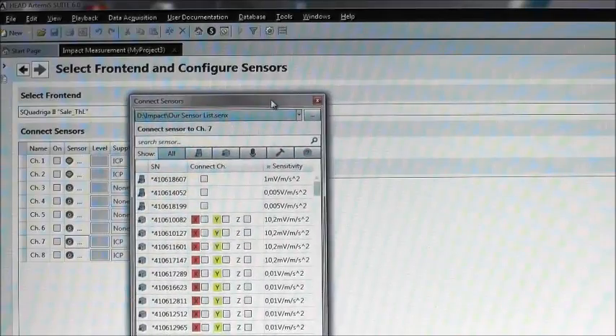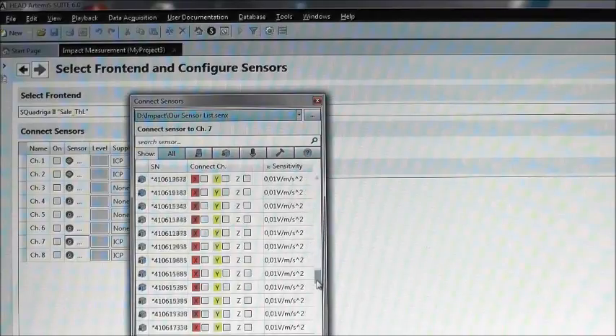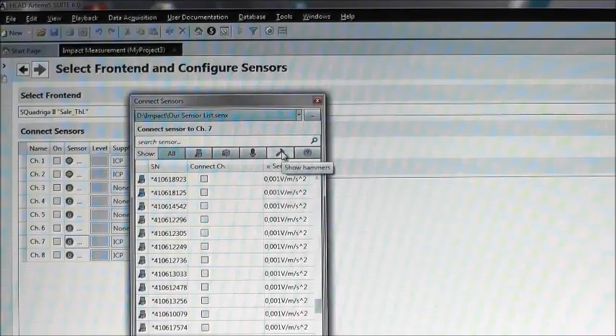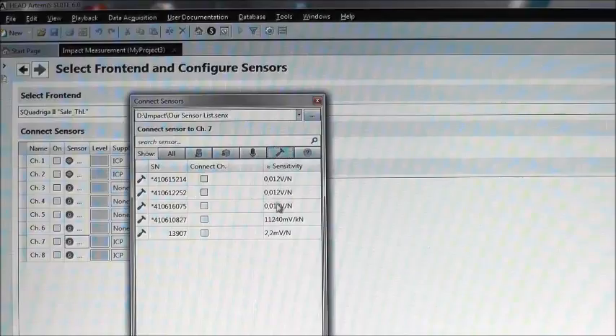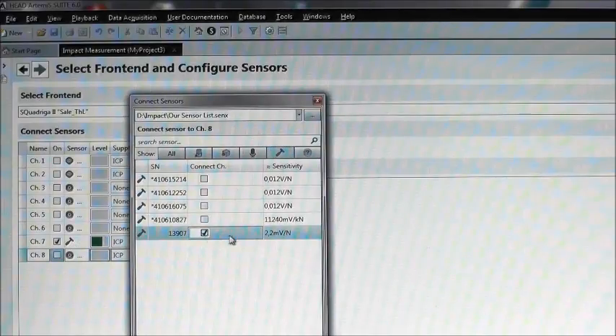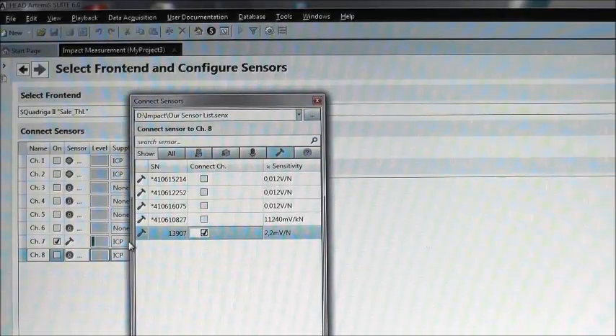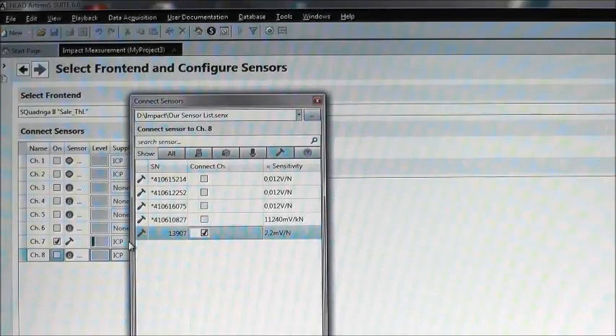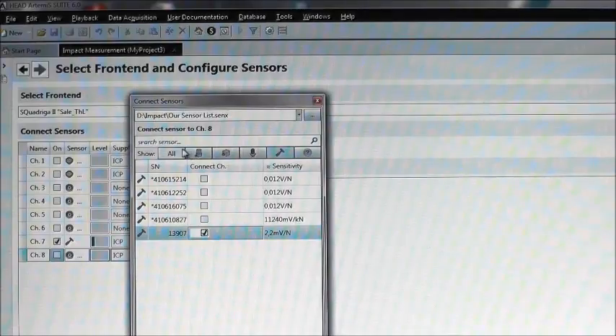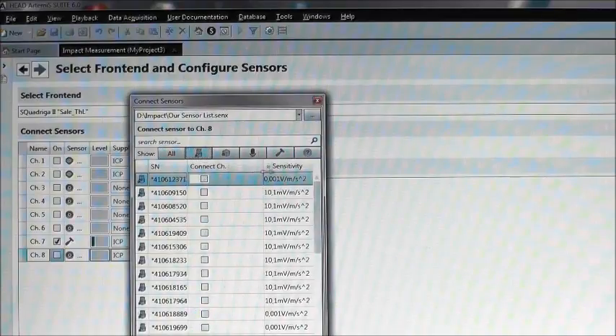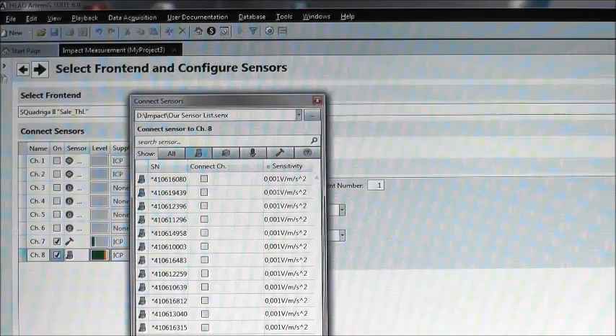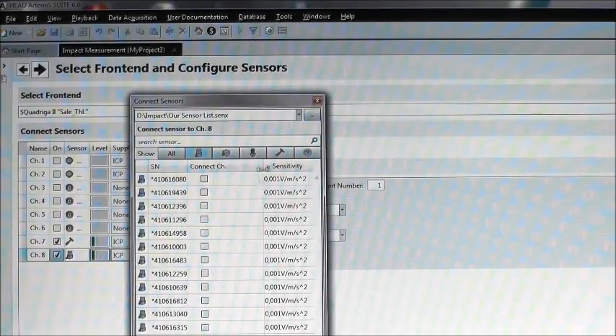If the list is rather long, like this one, we can use the filter functions to get a better overview. Clicking on the hammer symbol will show me my hammer sensors only. I am using the one with serial number 13907. Checking it, we will select it. Just checking whether it is working okay. I am seeing an excitation on channel 7, so let's proceed with channel 8. This is a uniaxial sensor, so I am choosing the corresponding view and search for my sensor. It is the one labeled 3079. There is a signal on this channel too, so both sensors seem to work correctly. We can close the sensor library now.